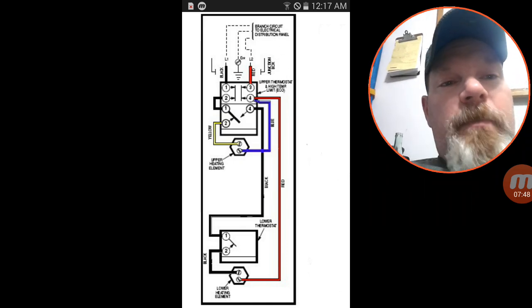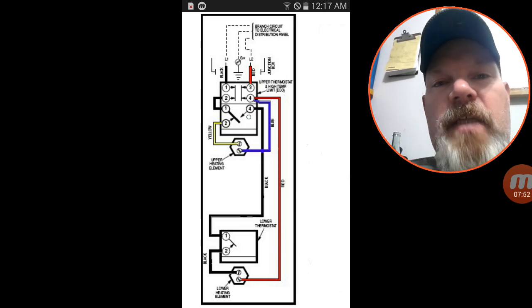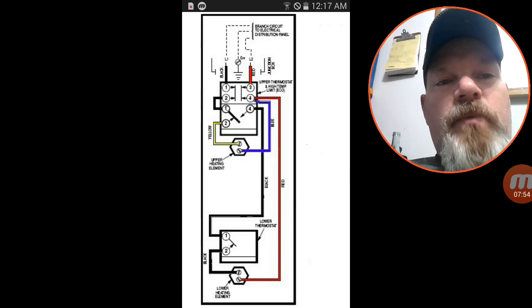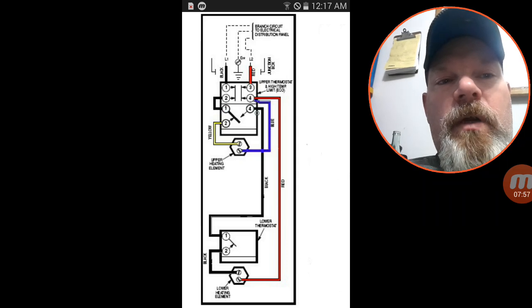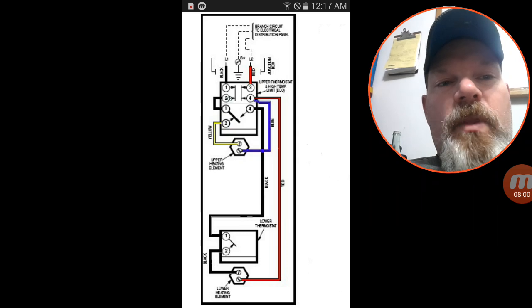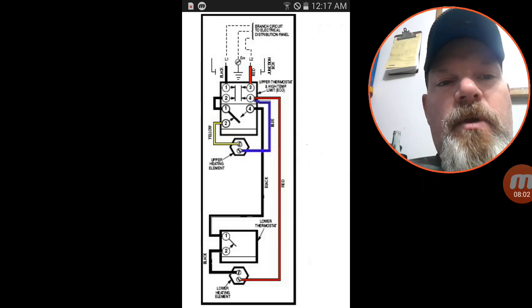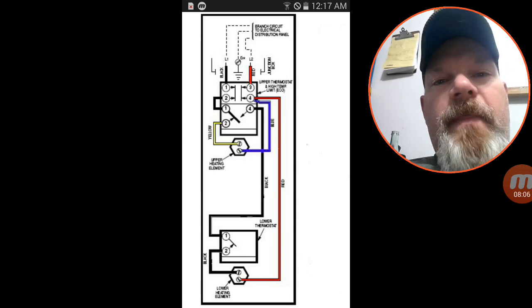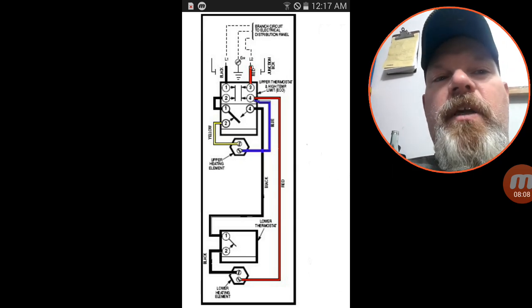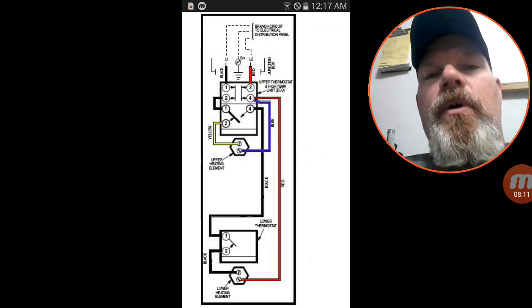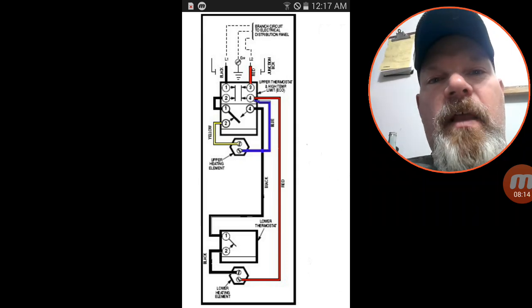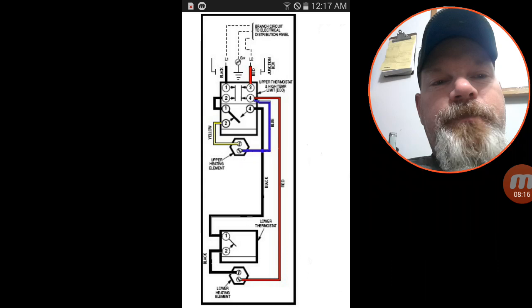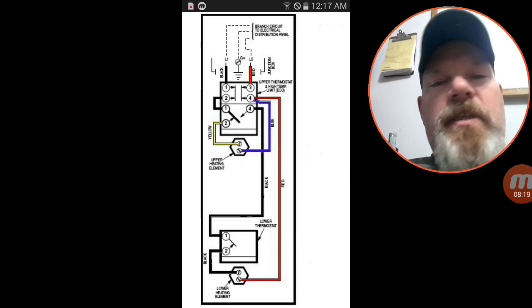What happens then? As soon as this thermostat senses that the upper portion of the tank is cold, this switch will switch from number one and number four to number one and number two. So then it is powering the upper element, and what that is trying to do is it's trying to recover the top portion of the tank to make that hot water available for as long as possible.